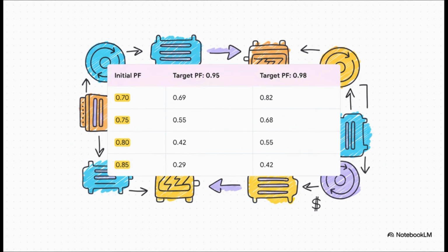Just find your current power factor in that first column. Let's say it's a pretty bad 0.75. Then find your target along the top. We're aiming for a healthy 0.95. The number where they meet, 0.55, that's your magic multiplier. You just multiply your total power in kilowatts by that factor and boom, you've got the exact size of the capacitor bank you need in kVAR.